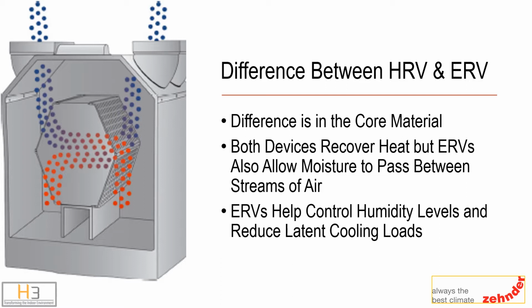One of the most frequent questions we receive relates to the difference between HRVs and ERVs. The main difference is in the core or heat exchanger material. HRV cores are made from non-absorbent materials. They recover heat and require a drain to channel condensate. ERV cores allow for absorption and redistribution of humidity. They may have a lower sensible efficiency, but they also provide latent efficiency, so overall they're even more efficient than an HRV. They help to moderate humidity in both dry and damp climates.